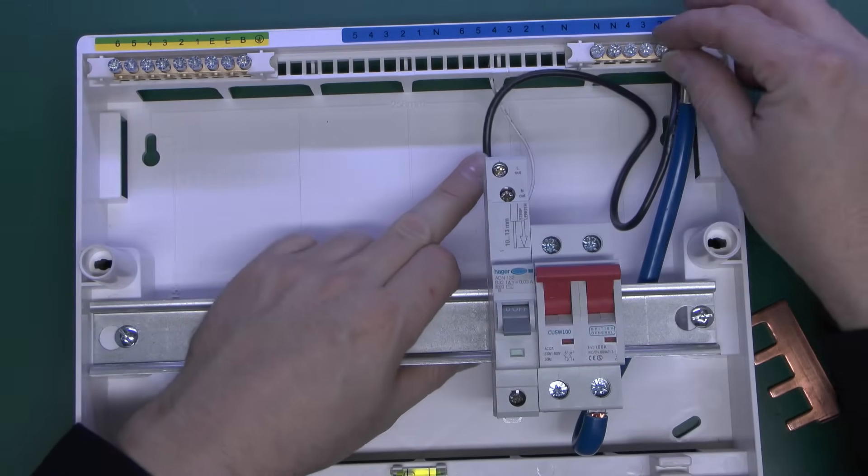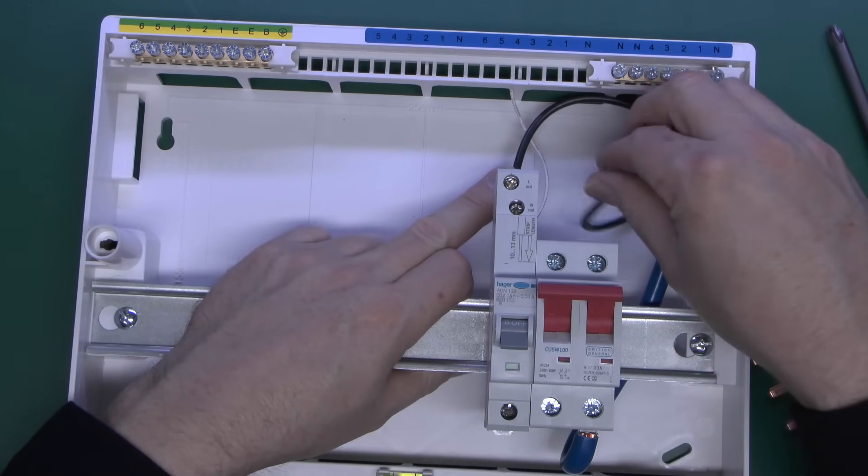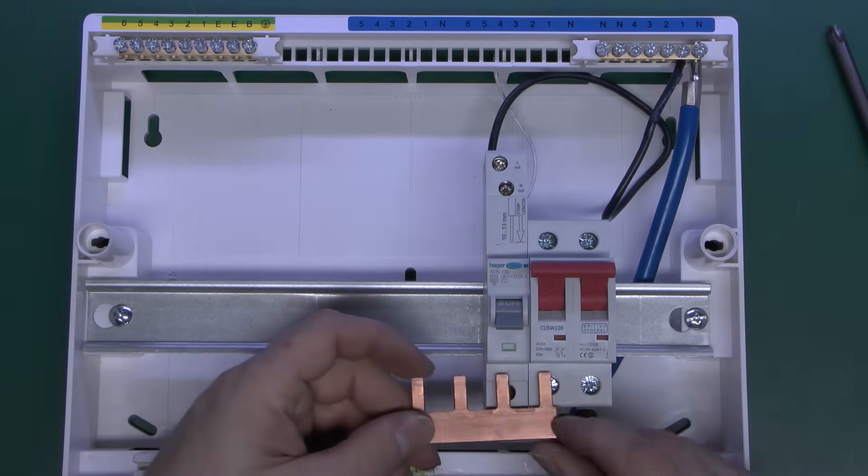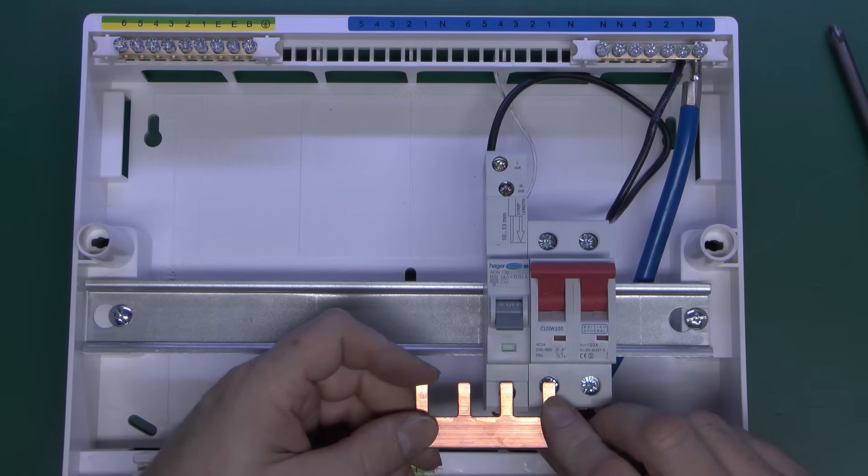So none of the circuit wiring actually attaches to the neutral bar it's purely only the flying lead from the RCBO which goes over there. And just as before the line bus bar just slots into the bottom here so connects across to all of the devices.